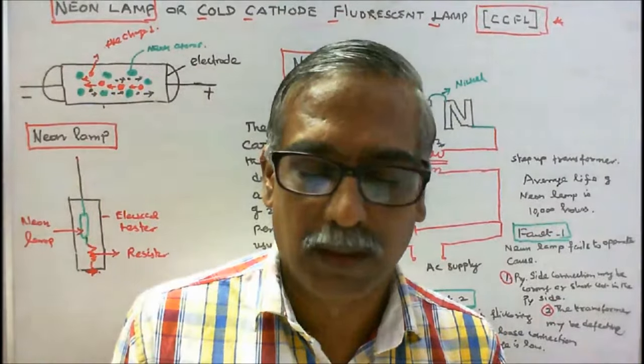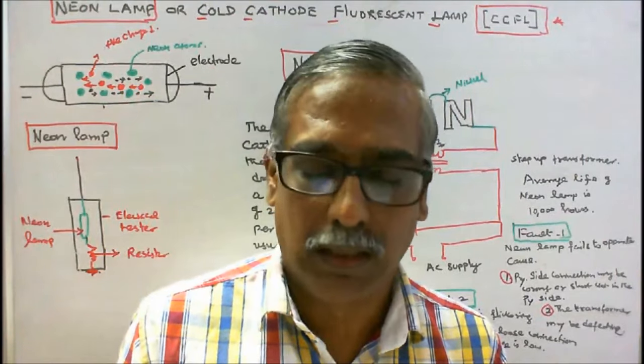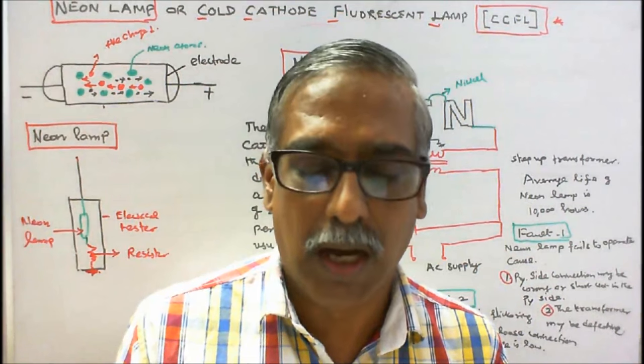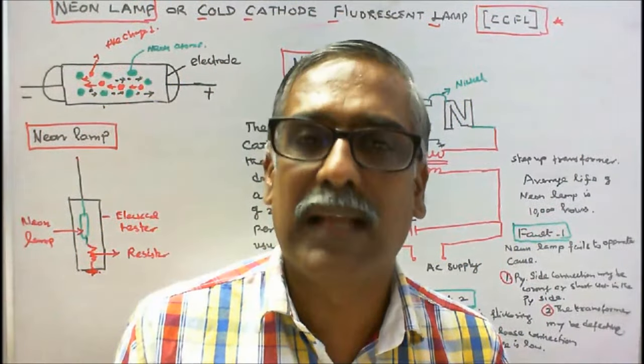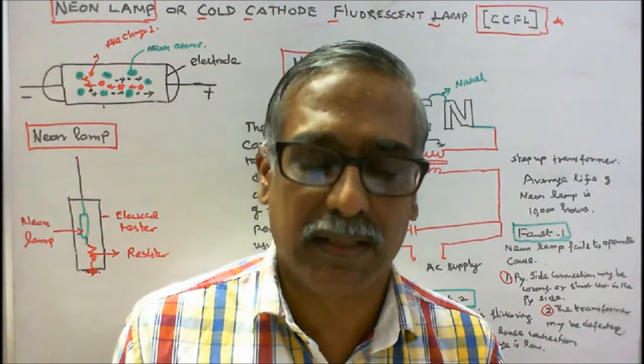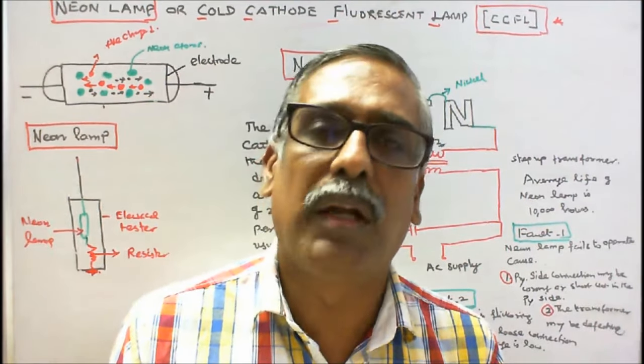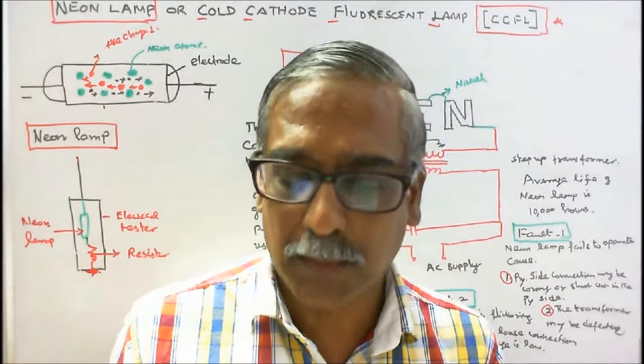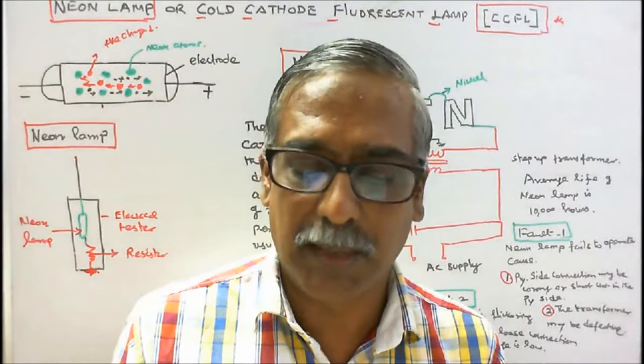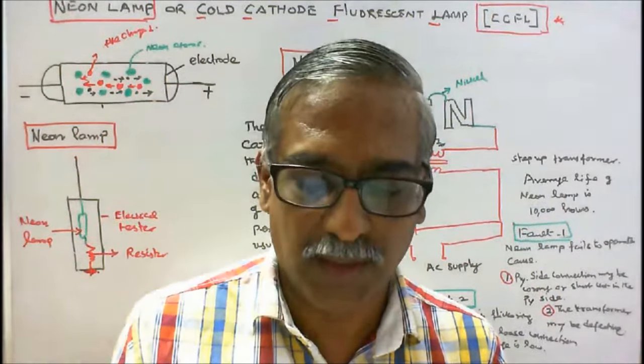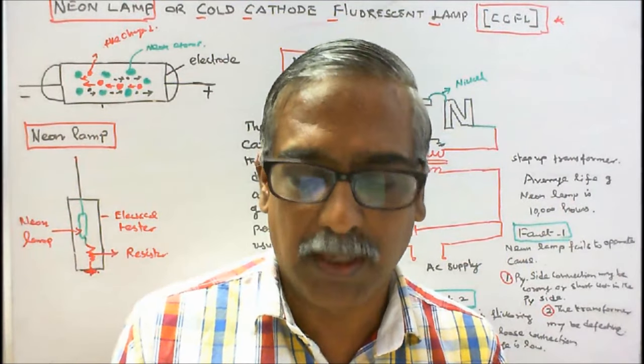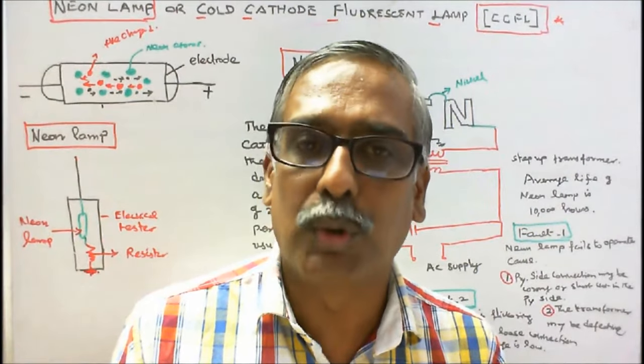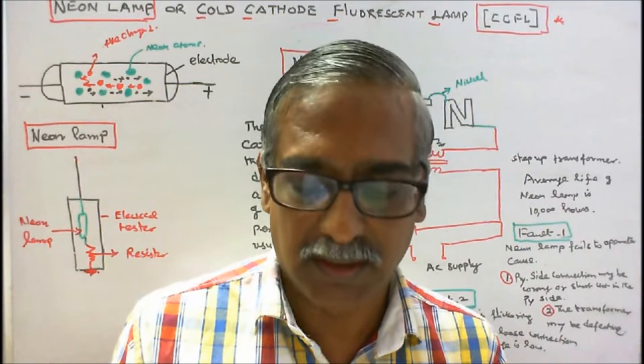The next type is neon tubes. These tubes are not used for lighting purposes but are used for advertising purposes as neon signs and letters. Neon tubes with varying lengths are employed for advertising and decoration. These lamps are called cold cathode lamps because their operating temperature is 200 degrees centigrade. The tubes are mounted either on a wooden frame or metal base and are matched with step-up transformers. The electrodes are made of copper, iron, or steel in a round shape, housed at the two ends of the tube filled with neon gas. Connections between letters are made by nickel wires. The step-up transformer secondary is grounded at midpoint for safety. The length of the tube may vary from 2 to 10 meters and may be bent into any desired shape during manufacturing.